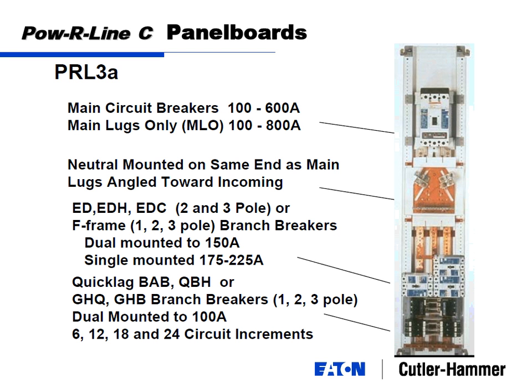This design, we actually have a neutral mounted in the middle, but we'll probably see that change here in the next couple of years from our standpoint. But down here is your chassis, where your feeder breakers are. Now you can see at the bottom are the same breakers that you have on your Powerline 1 or 2.